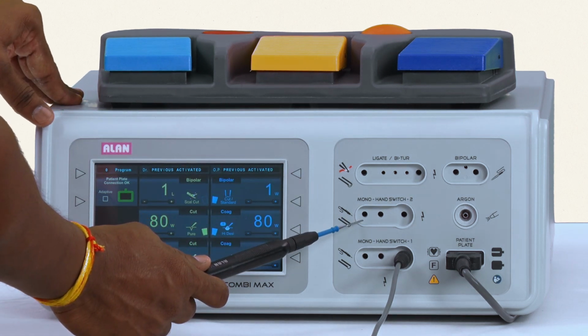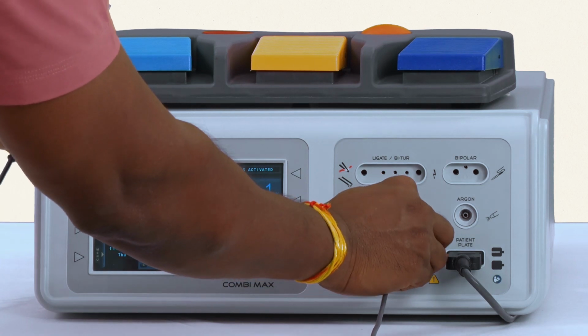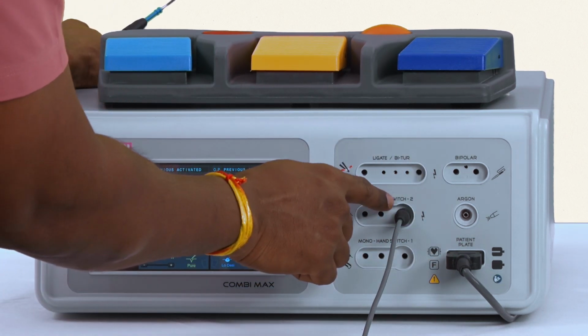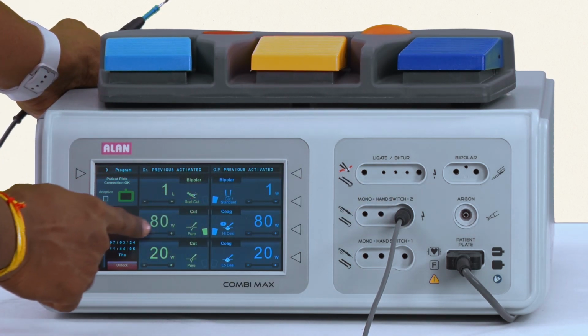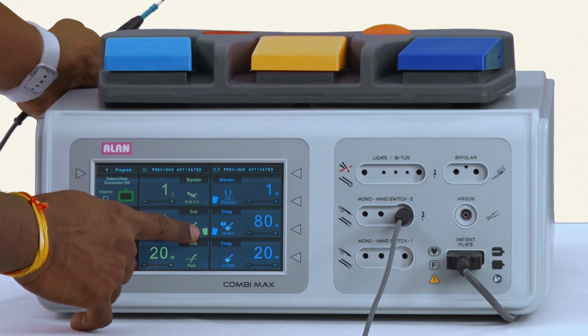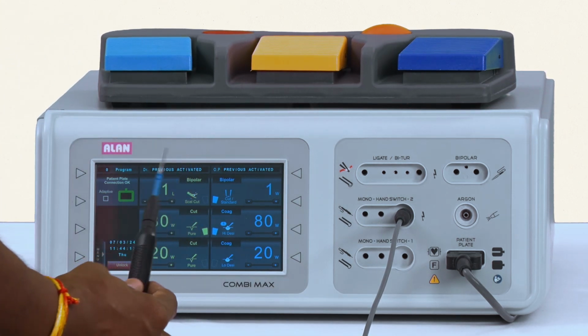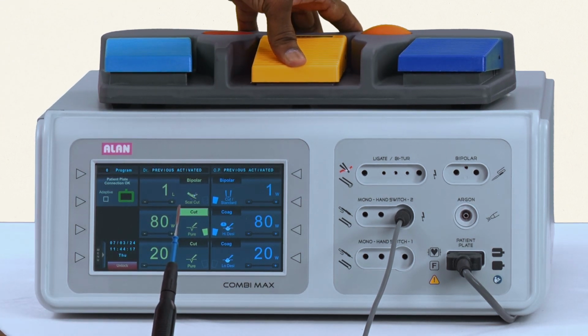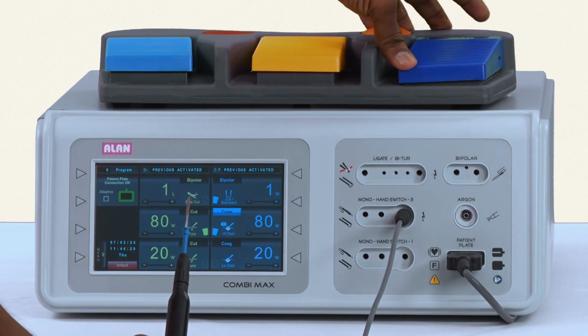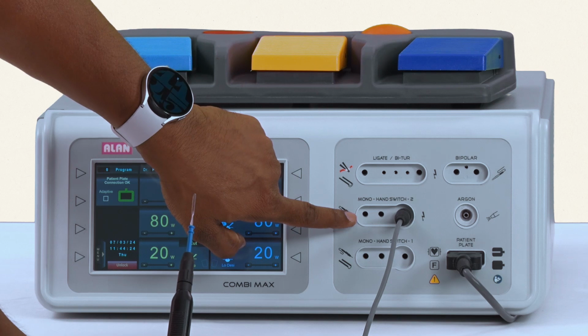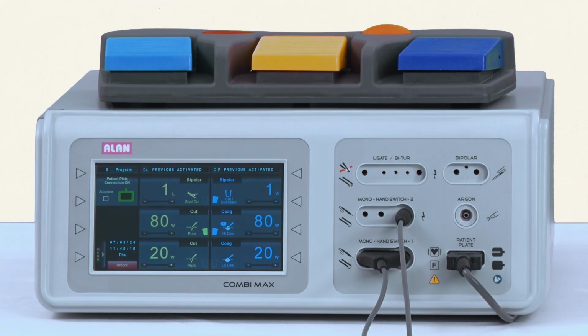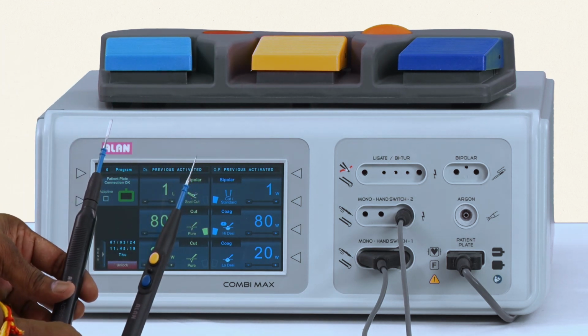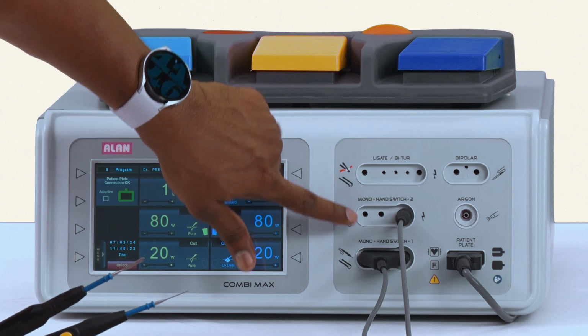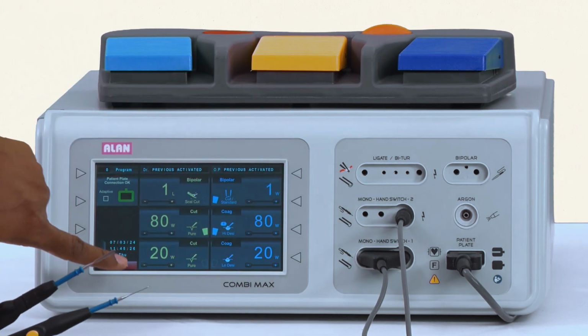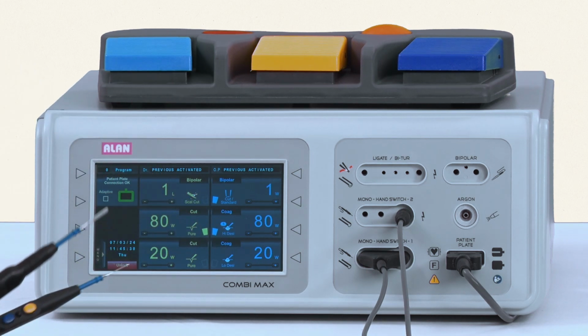this gets activated. Let's assume the surgeon wants to use mono hand switch 2. In such case, remove it from here, connect it to mono hand switch 2, and the corresponding mode will be changed here, the desired mode and desired wattages, and the foot switch selection should be here before activating. Now if I activate, see that respective cut and respective coag is getting activated, and the output would be coming from this mono hand switch 2. In scenarios where the surgeon wants to use 2 monopolar outputs at the same time, then they will have to connect 2 different instruments in mono hand switch 1 and mono hand switch 2, choose their desired mode and wattages and activate one after the other.